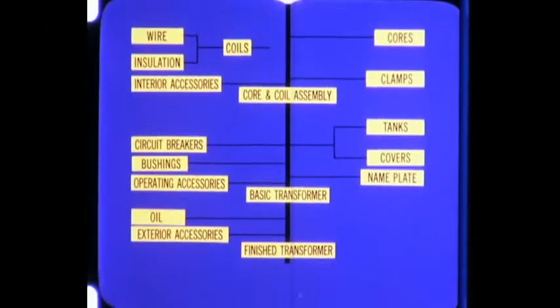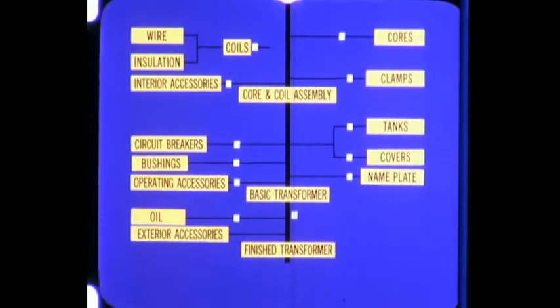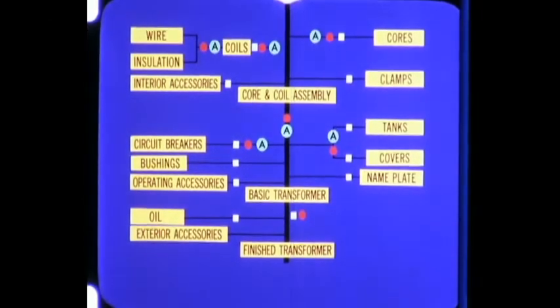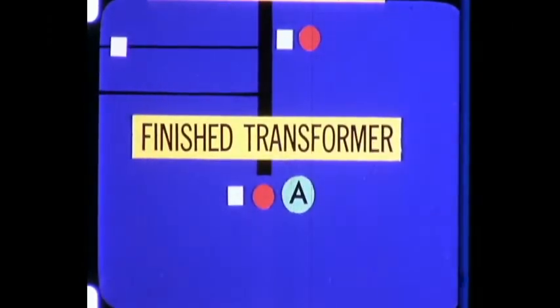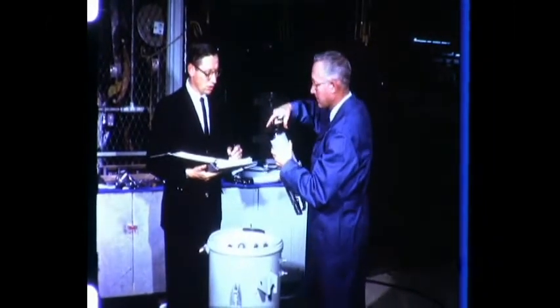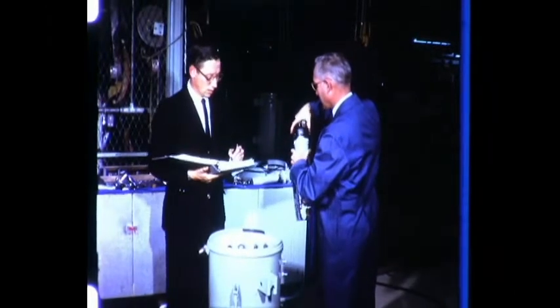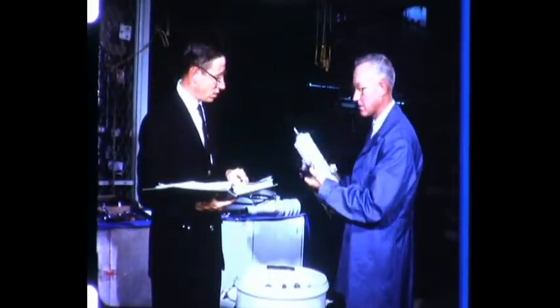This chart represents the total manufacturing process for distribution transformers. The many inspection points and in-process tests indicate the care and scrutiny a transformer is subjected to, culminating here in the final quality audit. Random samples of finished stock are disassembled and rechecked for such characteristics as tightness, alignment, location, finish, and correctness. Although all parts have been inspected and test operated, the total quality audit provides a most effective measure of quality control. This is part of total system reliability.